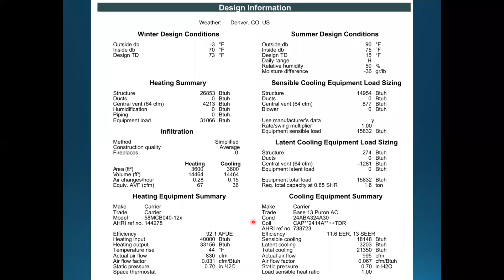So there's no, this is what it always is. You have to look it up for each unit. In this particular case, 44 degrees is within that spread. As long as in real life, regardless of what this math says, I put my temperature probe in there and I'm within the temperature rise, my furnace is working, period. Because when we get to altitude, which you guys don't worry so much about there, the fan speed charts don't work because it's all tested at sea level, guys. All tested at sea level. We'll get into this static pressure business next week when we talk Manual D. So let's move on.